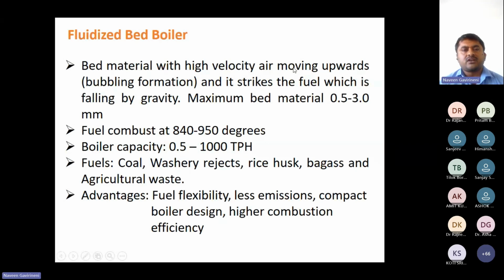As I have already explained, there is a bed material concept. The fuel does not combust directly in the boiler. There is a bed material arrangement. The bed material strikes the fuel while the fuel is dropping into the boiler. Then sudden burning does not happen. Layer by layer burning happens. The bed size is 0.5 to 3 mm, but mostly we use 1 mm only. As per OEM, they have given 0.5 to 3. The boiler combusts at 840 to 950. I showed this while showing that screenshot.